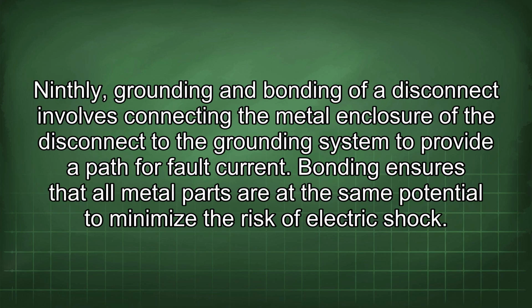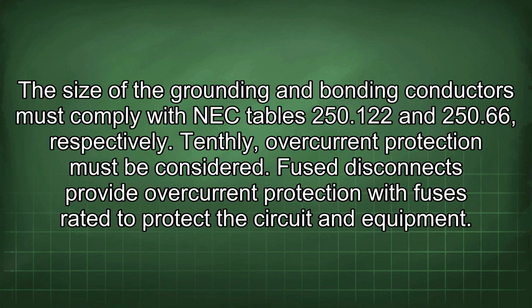Ninthly, grounding and bonding of a disconnect involves connecting the metal enclosure of the disconnect to the grounding system to provide a path for fault current. Bonding ensures that all metal parts are at the same potential to minimize the risk of electric shock. The size of the grounding and bonding conductors must comply with NEC tables 250.122 and 250.66, respectively. Tenthly, overcurrent protection must be considered.